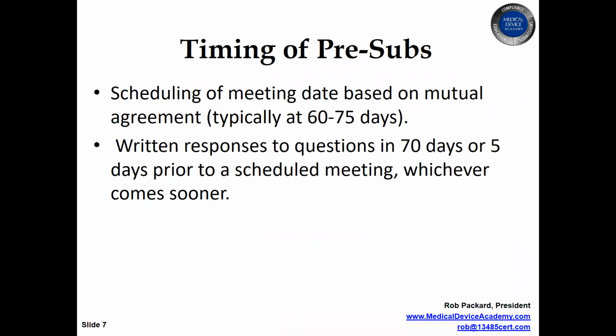So as I said before, for the timing of the pre-subs, they're targeting between 60 and 75 days for scheduling the meeting from the date they receive your request. And there should be a written response to all your questions in the pre-sub at 70 days or 5 days prior to your meeting. So if you schedule it at 68 days, you would hope to have a written response on day 63, whichever comes sooner. And these are calendar days.